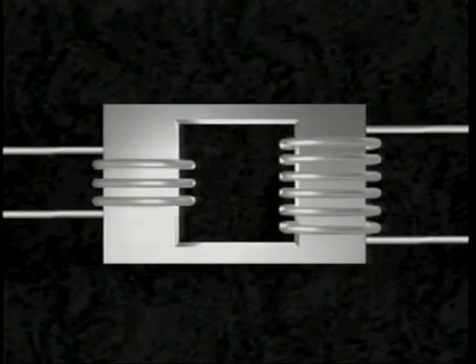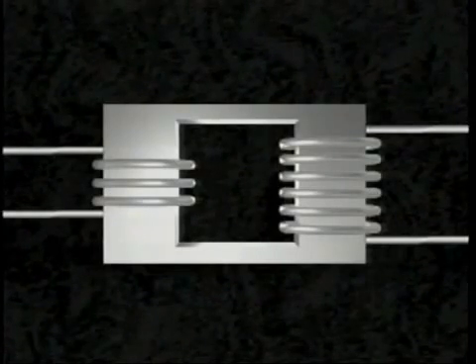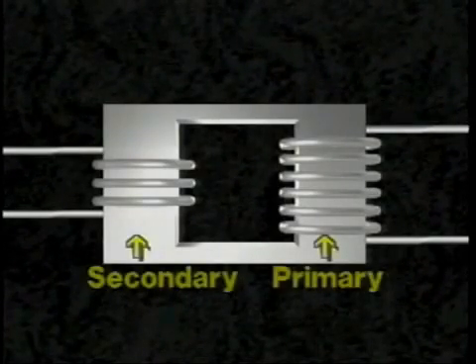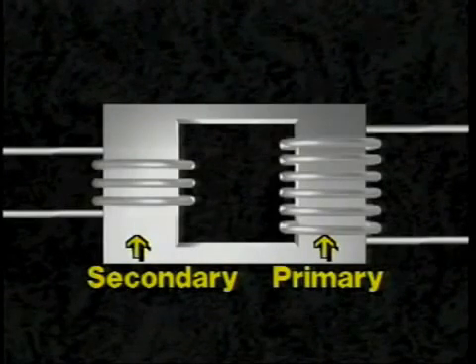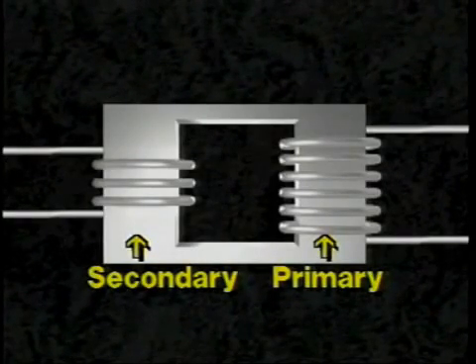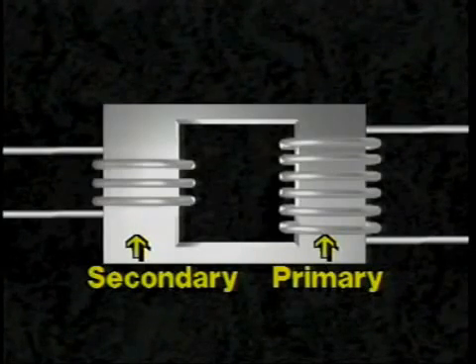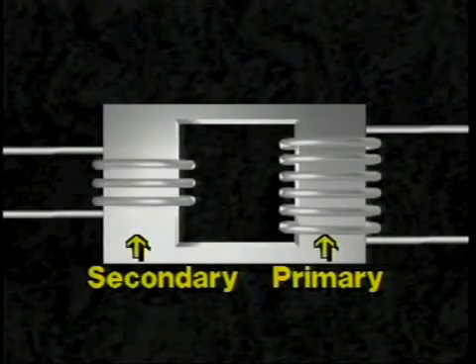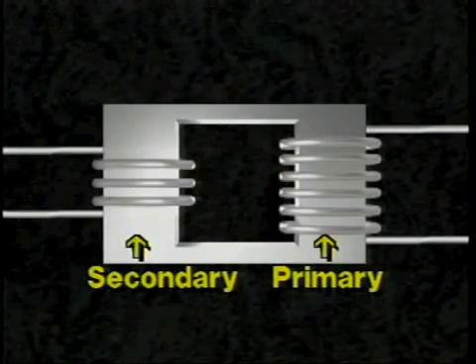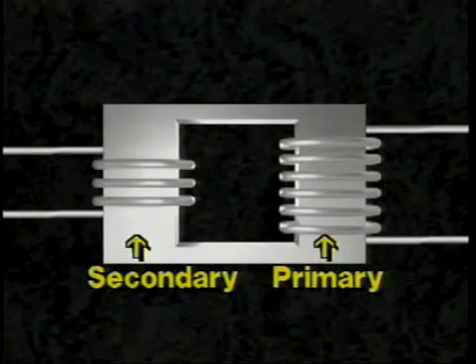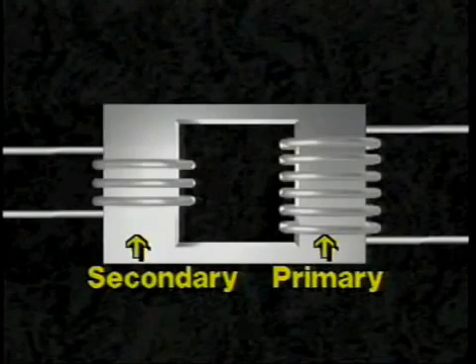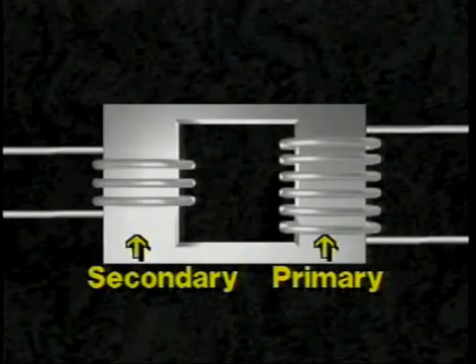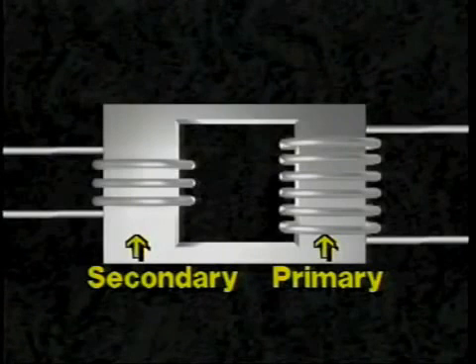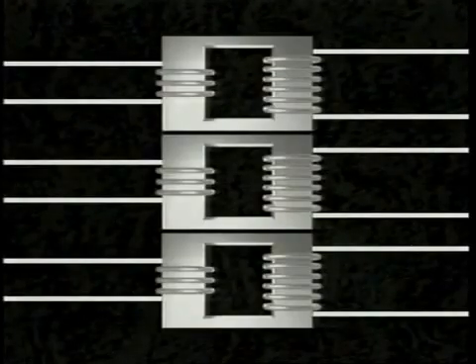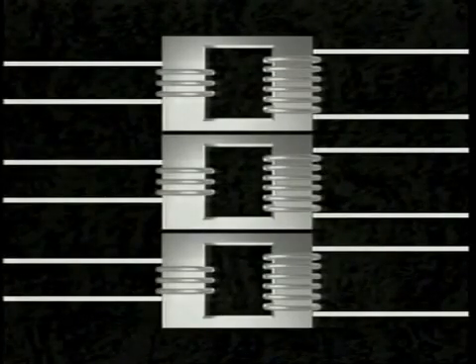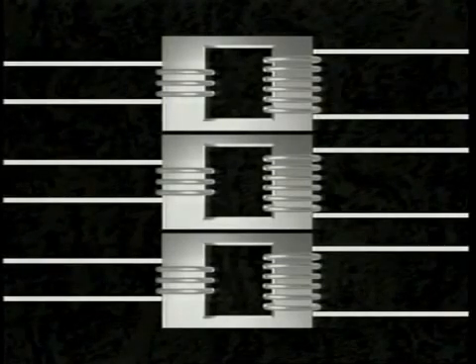A laminated square core of steel, specially made for this application, is wound with a primary and a secondary of insulated wire. The windings may be on top of each other or on opposite sides of the core. The capacity of the transformer is determined by the amount of cooling and the size of the winding conductors. Copper is the most commonly used conductor, though some aluminum is also found. A typical three-phase transformer has 6 sets of conduction coils, as shown here.